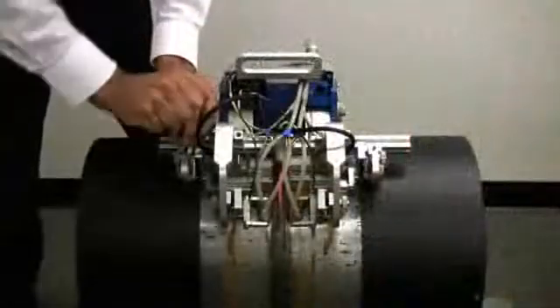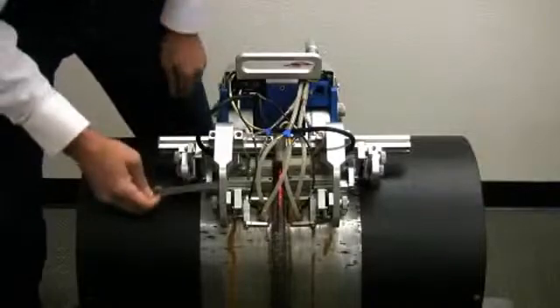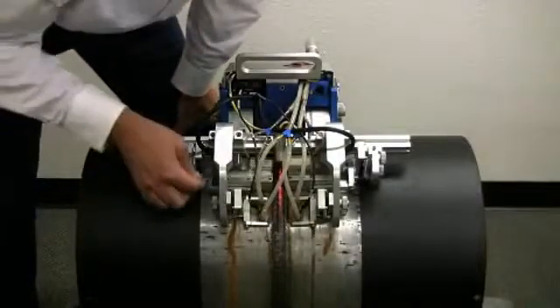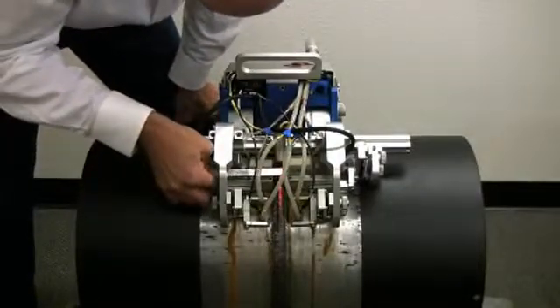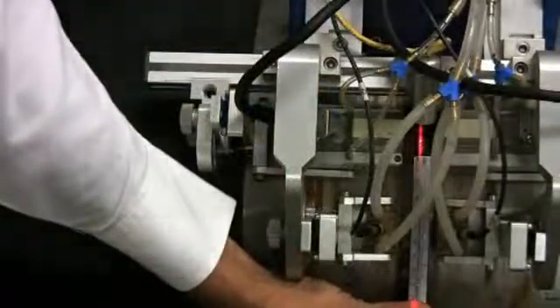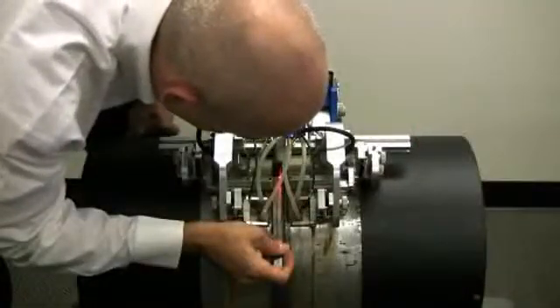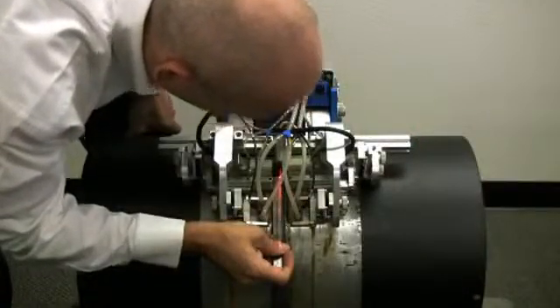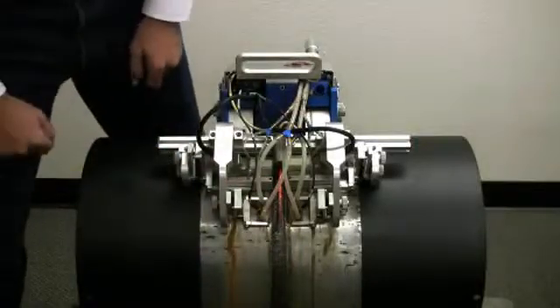Snub them down tightly, take a measurement of the center to center between the probes and take a measurement on the scan axis for the scan offset between the probes that will change with each diameter.